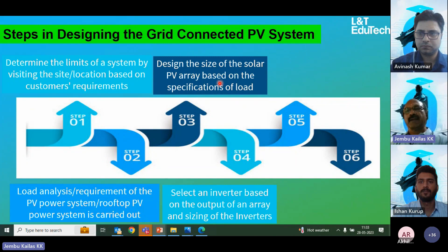Next is the grid interface. A very important thing to note is at what voltage level you are going to synchronize your system. You also need an agreement with the electricity board, since you have to connect to the electricity line. You have to check what line is available nearby, and your voltage depends on how much power you are going to produce.